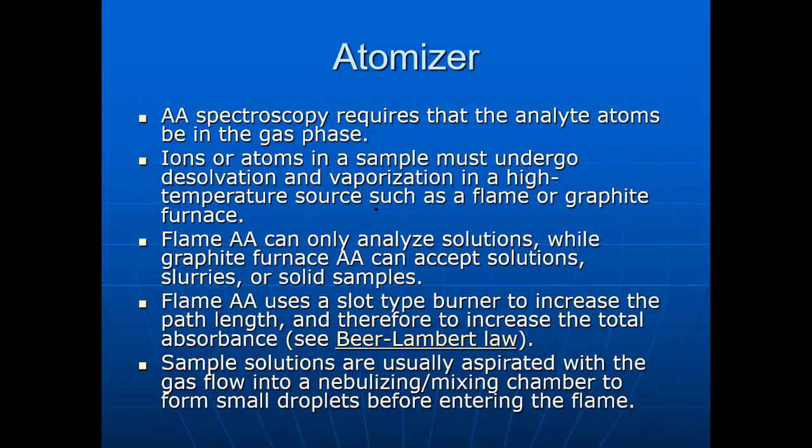So that vaporized sample can be analyzed by our instrument. The flame uses a slot type of burner to increase the path length and therefore increases the total absorbance. When the absorbance is more, we can calculate it. The sample solutions are usually aspirated with the gas flow into the nebulizer mixing chamber to form small droplets before entering the flame.